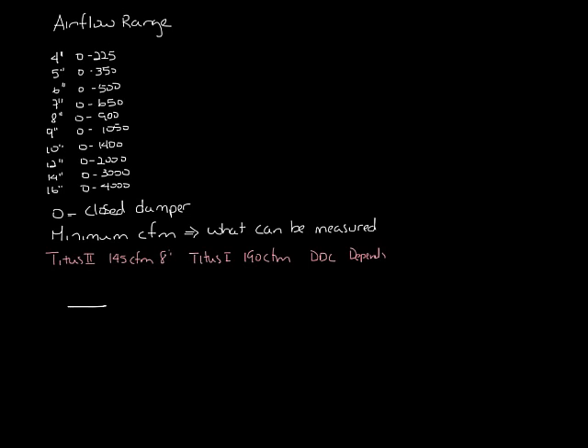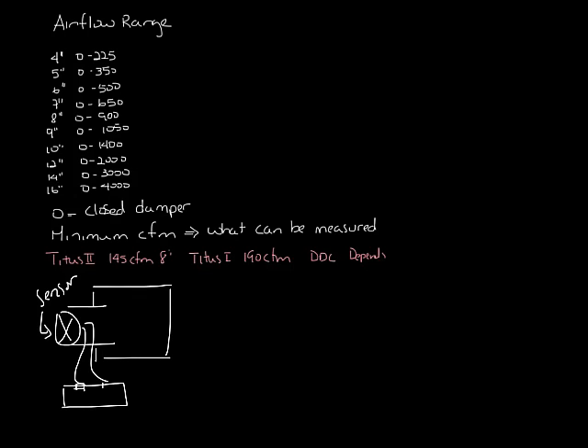It's actually connected to pressure ports on a pressure transducer in the controller. So let me draw a VAV box real quick. There's the unit casing, inlet, and then your flow sensor's in here. One side is connected to the total pressure side of the flow sensor, and the other side is connected to the static pressure side.